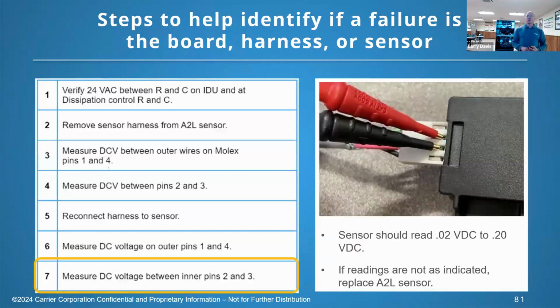And then finally, with the sensor connected, measure the inner 2 pins, and you should be seeing about 0.02 to 0.2 volts DC fluctuating. And if that's not changed from before, then you have a bad sensor. Okay. On the question asked about the communicating system, will it show a fault on the thermostat, the wall control? Yes, it'll show a fault on the wall control.